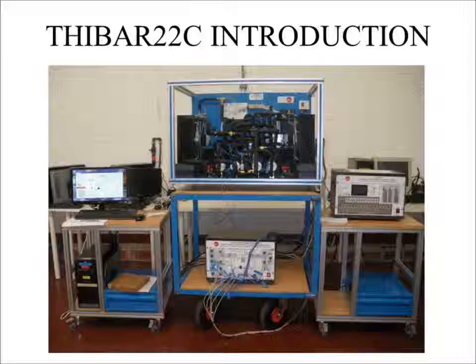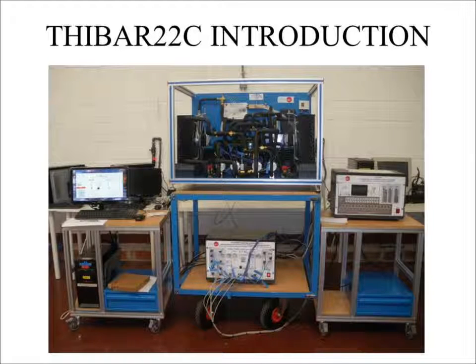In this video, we're going to be discussing the Edibon THIBAR22C series computer control heat pump, air conditioner, refrigeration unit with cycle inversion valve. The THIBAR22C is a computer control unit designed to study heat pump performance and also the changes in the refrigerant condition, just like water and air, allowing the study of the coolant circuit. The heat pump, the cooling or air conditioning equipment are basically created of that cooling circuit. This unit has a water condenser and an air evaporator installed to allow water warming and/or air cooling. If both of them are selected for a particular task, water warming and air cooling will occur.